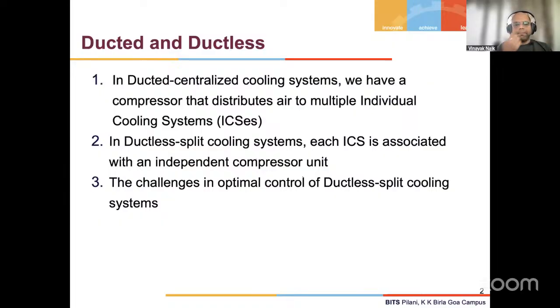The usual way of running these ACs — which I've also seen in many industrial systems, like corporate offices or banks — is to switch on all the ACs in a room at minimum temperature with maximum fan. That's the easy way of doing things. But the room is very large, and the heating load can vary from one corner of the room to another.